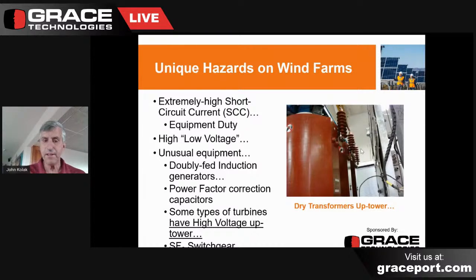And finally, the type of switchgear you'll find on a wind farm is often sulfur hexafluoride switchgear. Identical switchgear that you see on a solar farm, and it's used in this case on a wind turbine generator. So again, it requires special training for both lockout, tagout, and grounding. Let's go to the next slide.